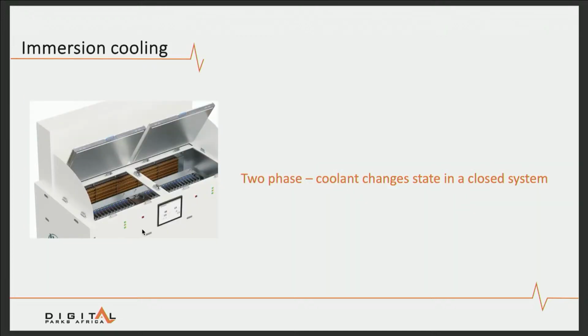Then I mentioned also the two-phase cooling. The two-phase cooling is very similar. It's a slightly different approach. The liquid is a liquid that has a relatively low boiling point. So in the two-phase immersion system, it's essentially a closed system. The coolant actually boils at about 50-something degrees, evaporates, and the evaporated liquid is passed through a number of condensation coils, and those condensation coils create the condensate again, and the liquid returns to the tank where it's circulated.